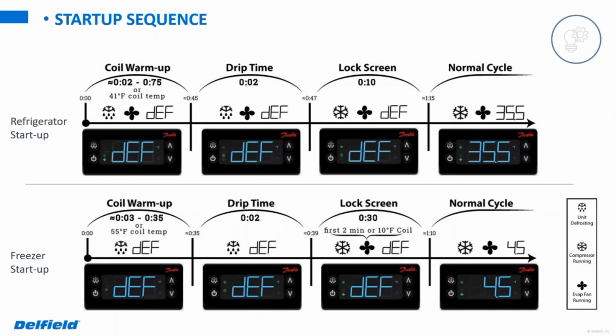The big thing being that time after defrost on both the cooler and the freezer, where you're going to see the unit running, a call for cooling, but showing that DEF on the display. That is normal operation for these, so just something to be aware of on that. More often than not, it's not going to be an issue.